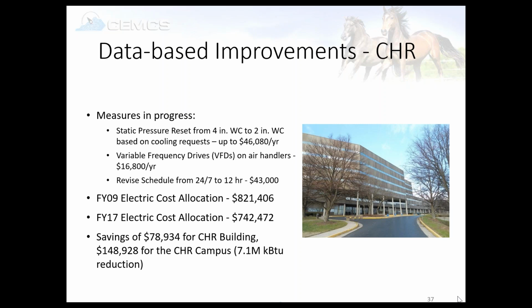They're actually going to be doing a capital project replacing all of the VAV boxes through the building, and that's driven by the fault detection program that we have installed in the building automation system. And using the data from that, we can see that most of these VAV boxes are way past their useful life. So that's kind of driven a large capital project. We've added VFDs on the air handlers, the supply fans. There were 4 of them. They were 125 horsepower.